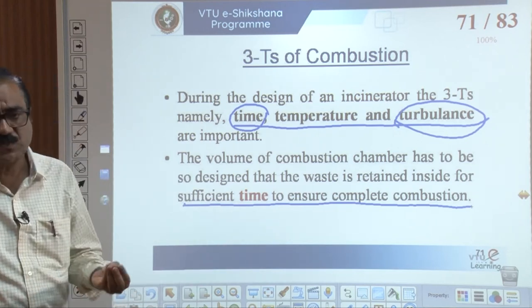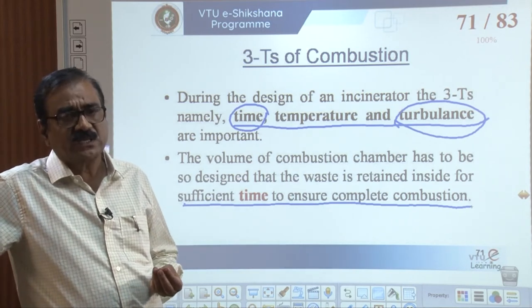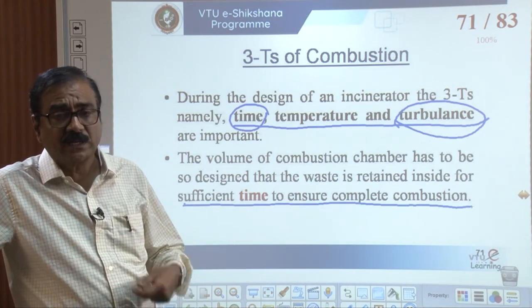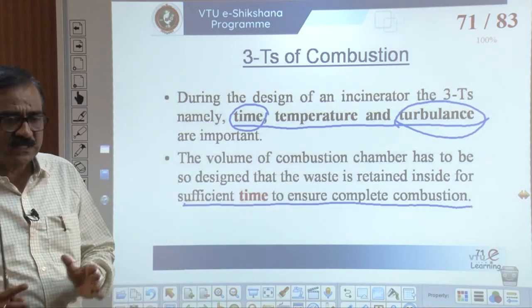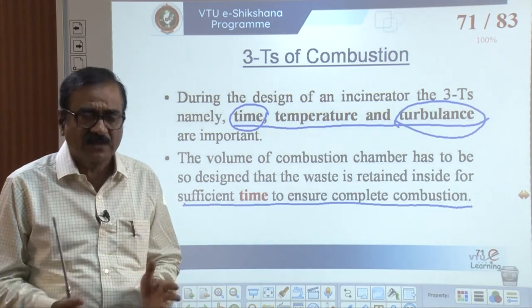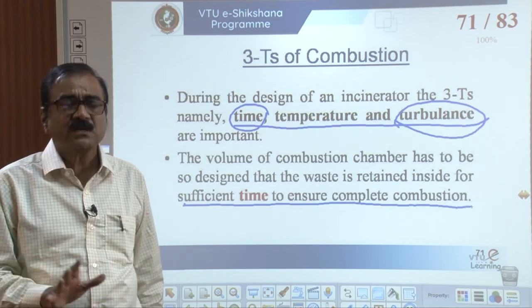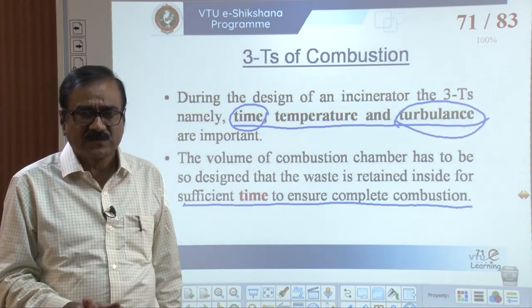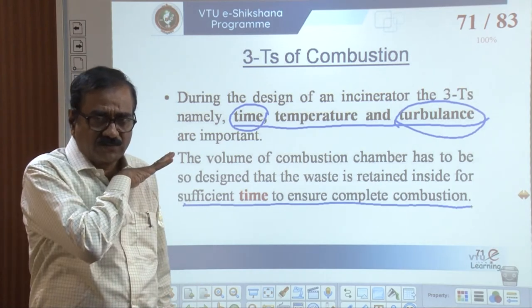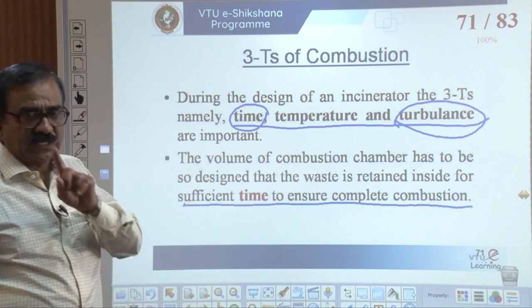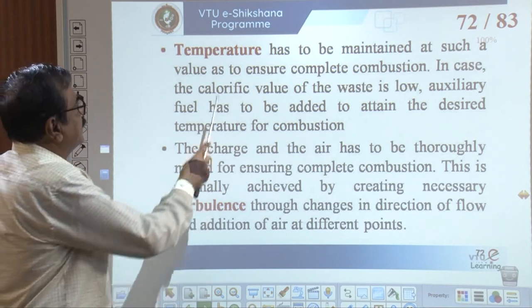The first T — time — means that sufficient time should be given so the municipal solid waste is retained within the combustion chamber long enough from the charging chute through the furnace until it goes out. The second T is temperature. The temperature must be maintained at a value that ensures complete combustion. If the calorific value of the waste is low, auxiliary fuel must be added, as discussed in the three-component diagram.